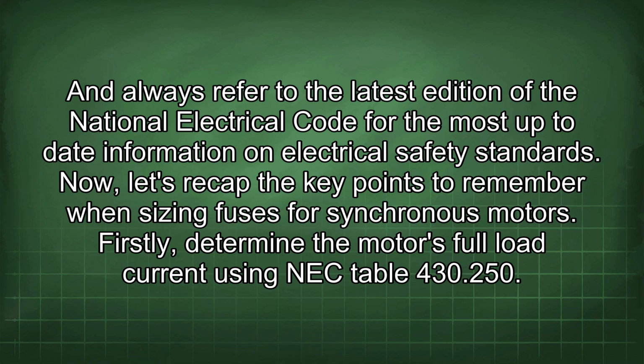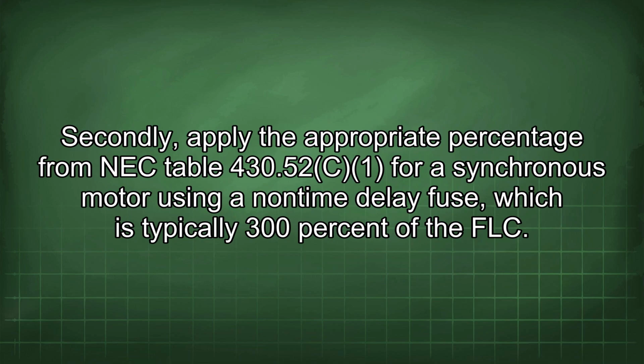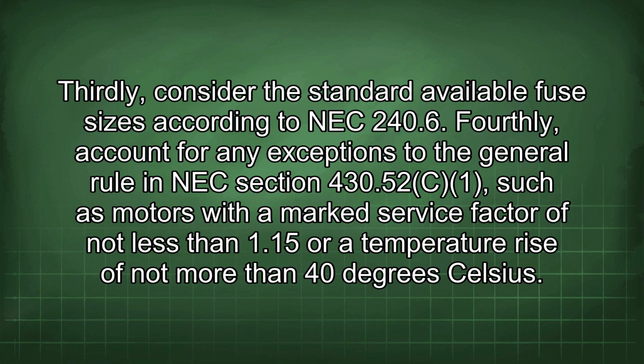Now, let's recap the key points to remember when sizing fuses for synchronous motors. Firstly, determine the motor's full load current using NEC Table 430.250. Secondly, apply the appropriate percentage from NEC Table 430.52 for a synchronous motor using a non-time delay fuse, which is typically 300% of the FLC. Thirdly, consider the standard available fuse sizes according to NEC 240.6.